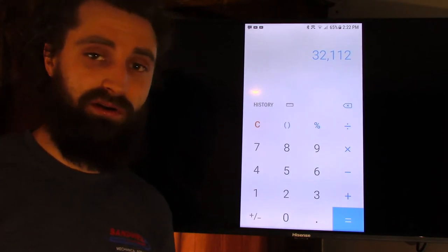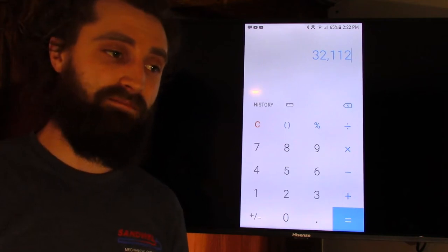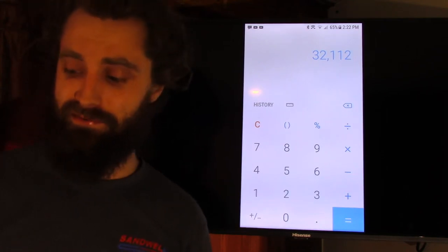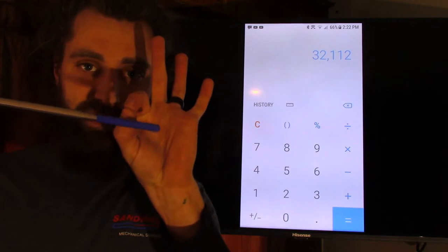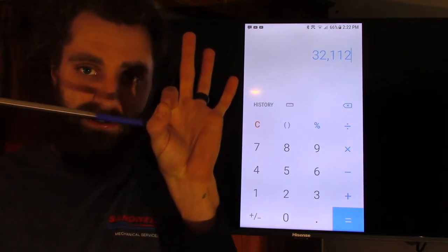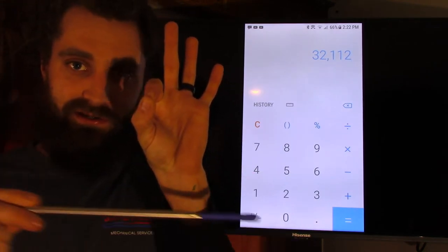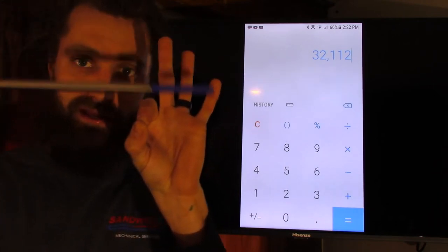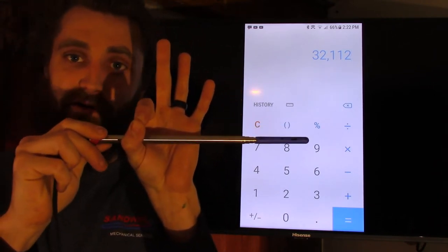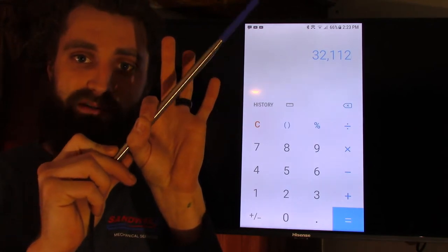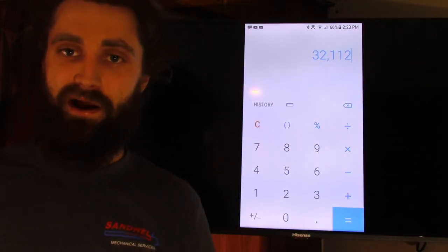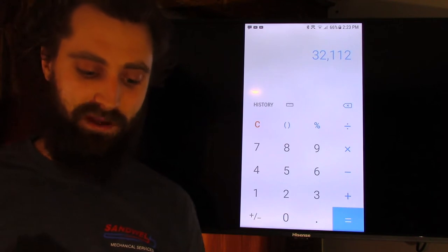Or you could say, I wasn't really taking a good airflow measurement. Maybe I should go back and take another good airflow measurement, because with the hot wire anemometer, you've got to remember that this probe, you can't just jab right into the supply. You've got to actually traverse that duct in several different locations and average those readings out, okay? Because right in the center, you're going to get a really high velocity, out towards the edges, okay, and like down in the corners, the air is just kind of tumbling across that fiberglass or that liner or even the sheet metal.